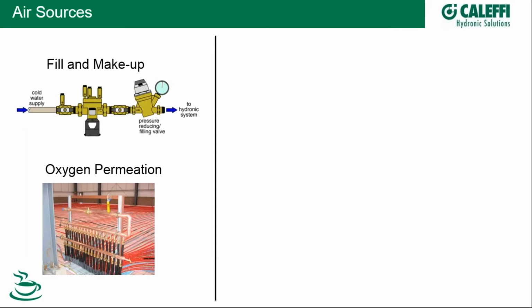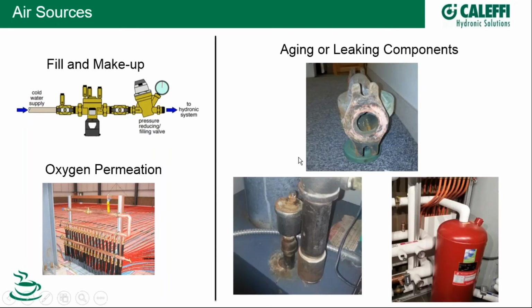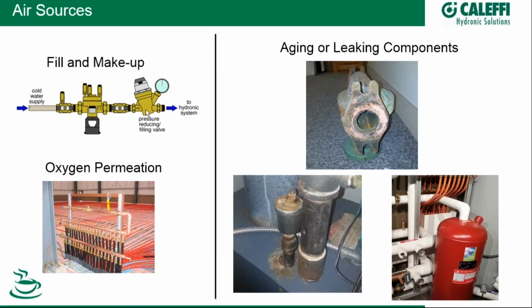So oxygen is going through the walls of that type of polymer by way of osmosis. It's very interesting, but it actually happens. Also, as the system ages and gaskets start to wear and develop leaks, and O-rings, as that water or fluid leaks out, it's an opening for air to get in. But probably more importantly, as water leaks out, your pressure reducing valve or your pumping makeup cart is going to sense that and open up and allow cold water in, in the case of a straight water system. And that water is going to have oxygen. So those are air sources that we have to be concerned with.